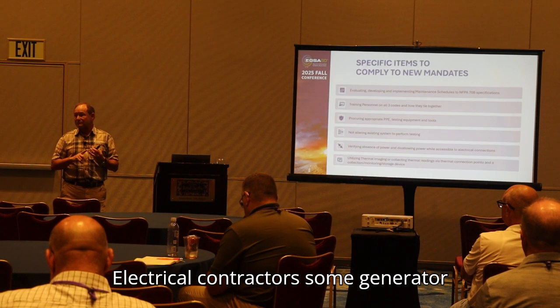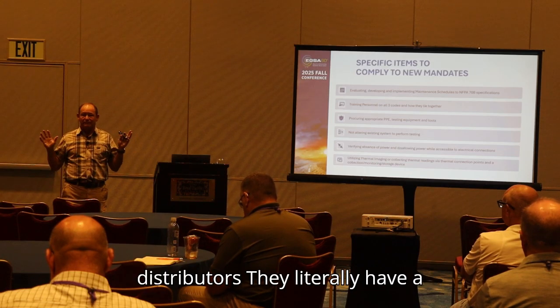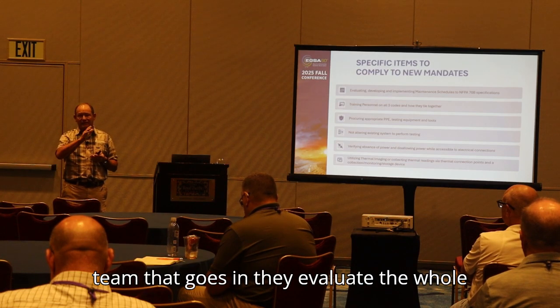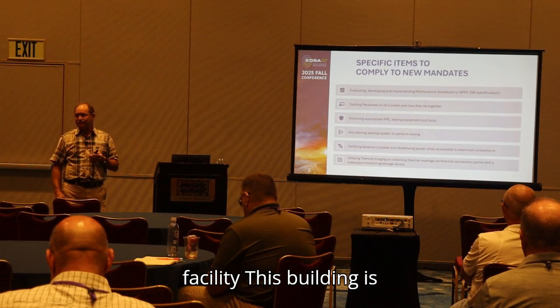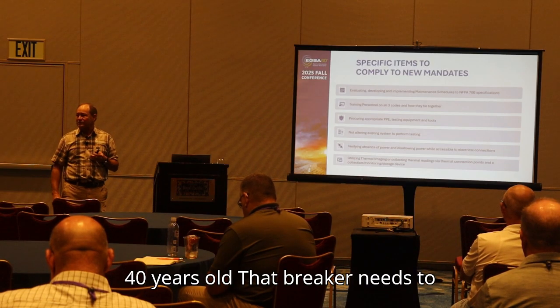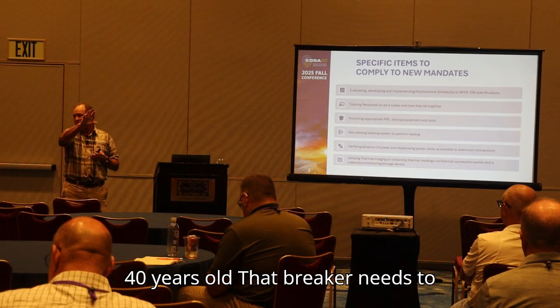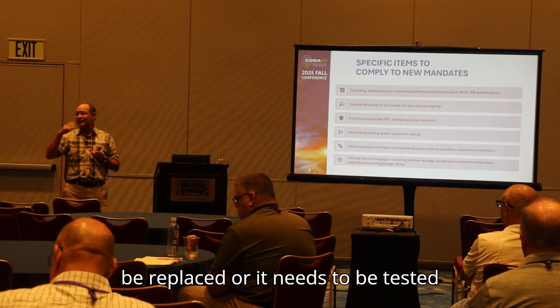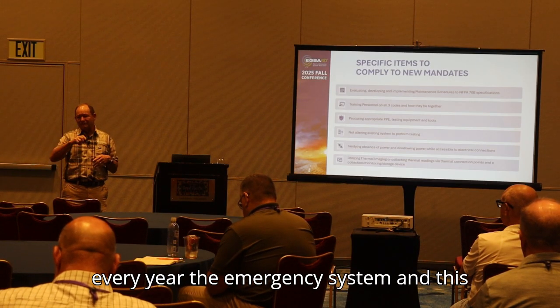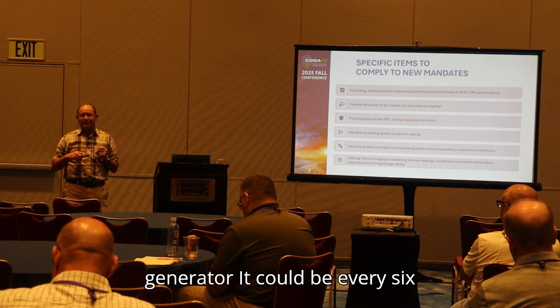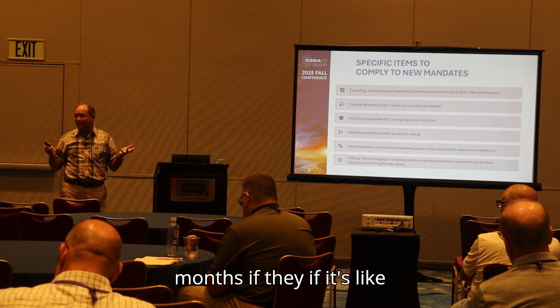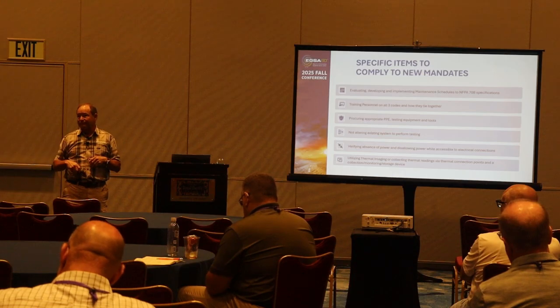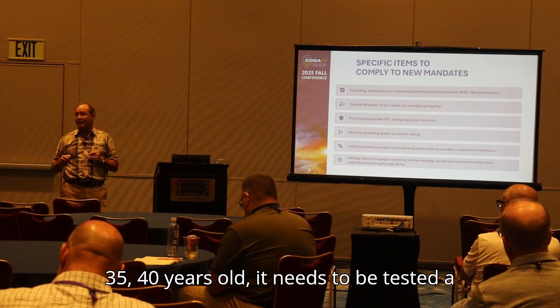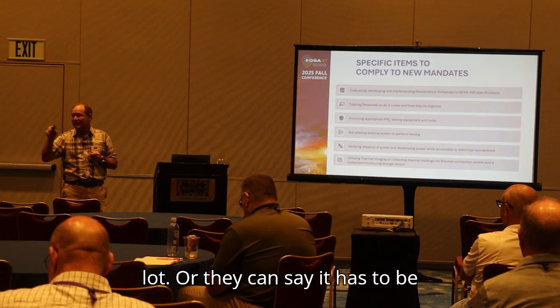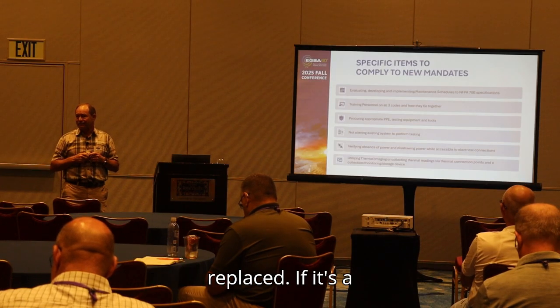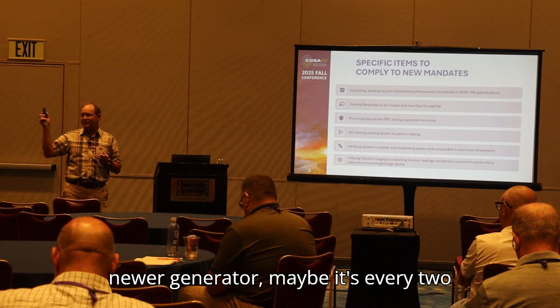Electrical contractors, some generator distributors, they literally have a team that goes in and they evaluate the whole facility. This building is 40 years old. That breaker needs to be replaced, or it needs to be tested every year. The emergency system and this generator, it could be every 6 months. If it's like 35, 40 years old, it needs to be tested a lot, or they can say it has to be replaced. If it's a newer generator, maybe it's every 2 years.